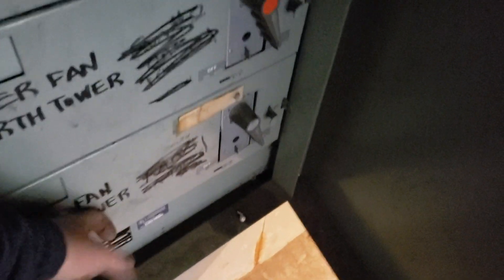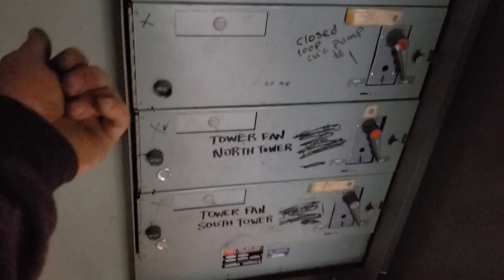There's no hand-off auto switches anywhere. It just has the contactors, motor starters in here. Again, no auto-off-hand. So it's always been a pain in the ass to run this system.